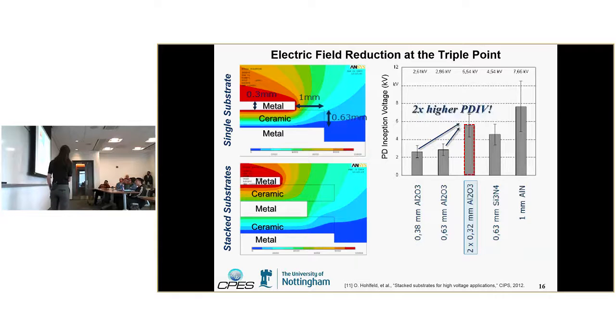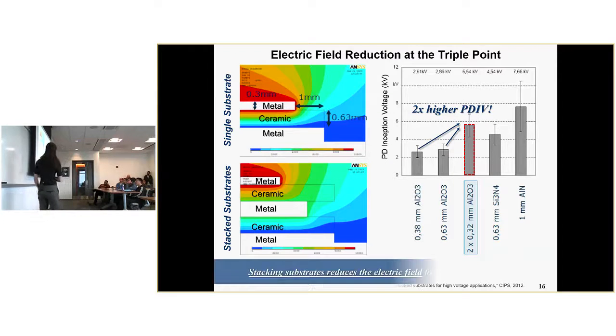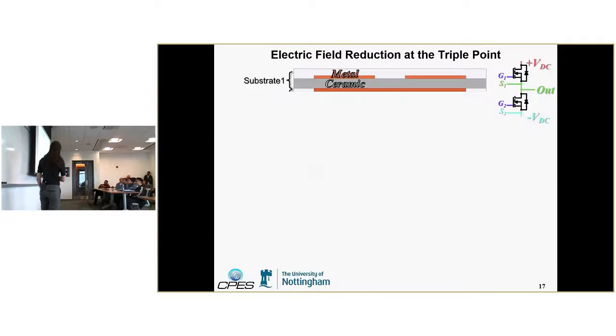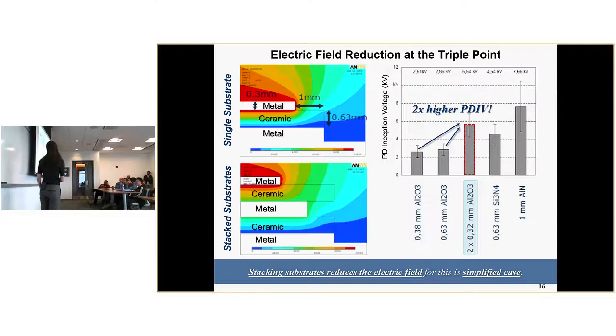And you can see that when you have two stacked ceramic substrates, you actually get 2 times higher partial discharge inception voltage. So what that means is that instead of seeing partial discharge at 3 kV, you're now seeing it closer to 6 kV, which is a significant increase. Okay. But this was kind of an oversimplified case.